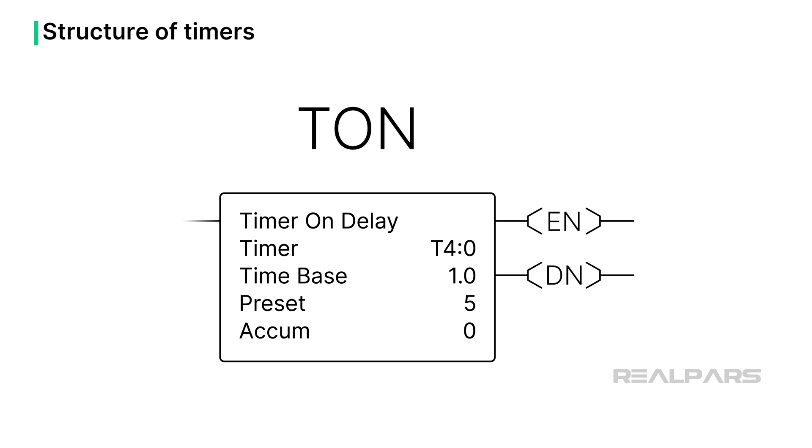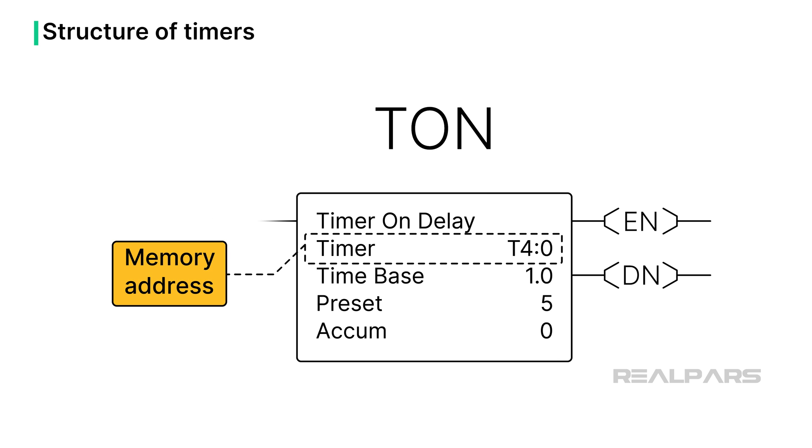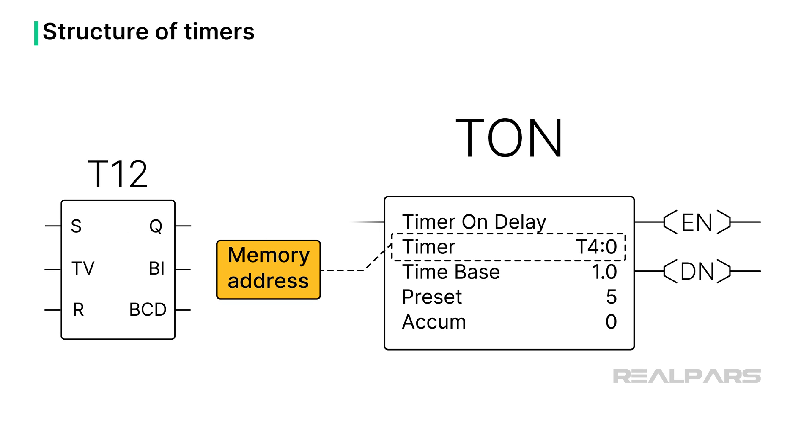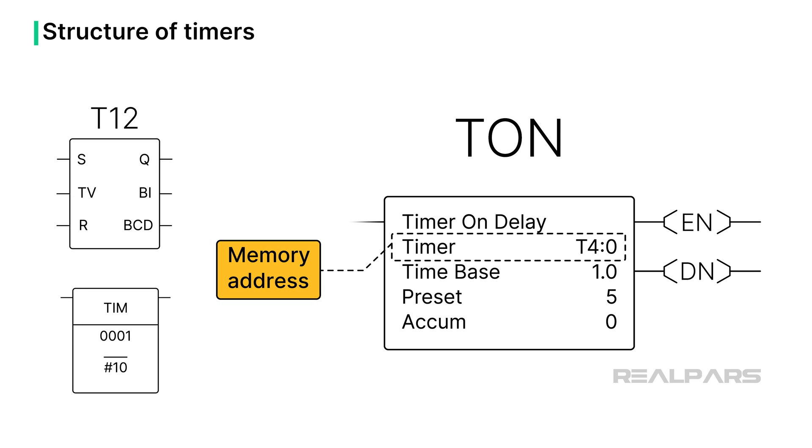Timers all have a basic structure. I will illustrate this using an IEC on-delay timer shown here. Timers all have a memory address. In this example, the address is T4:0. Depending on the PLC model, this address can be a file number and element as shown here, a simple timer number such as T12, or a numeric address.